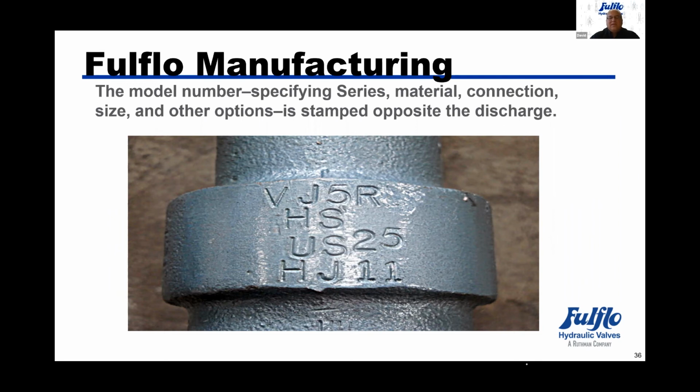The US is the spring. Range on the US spring is 7 to 35 adjustable, but here the customer wanted us to set it at 25 PSI. So it was set to 25 before we ship it out the door.